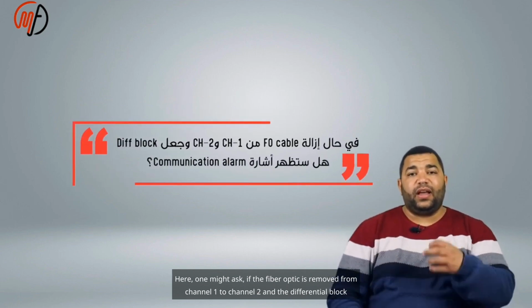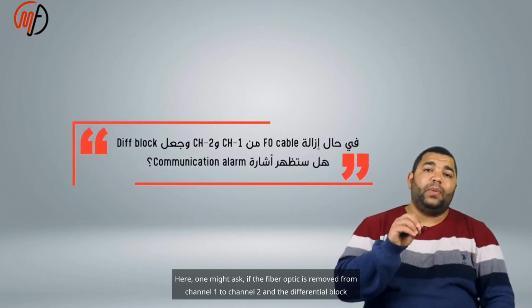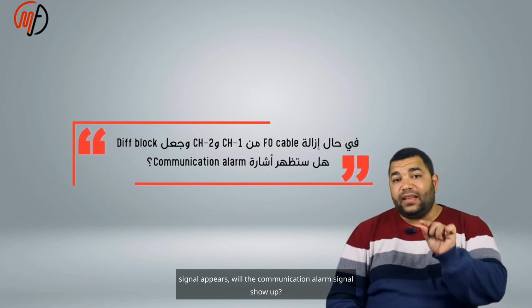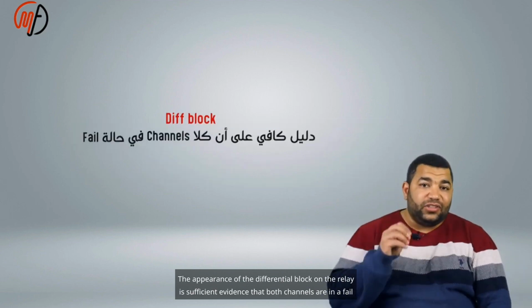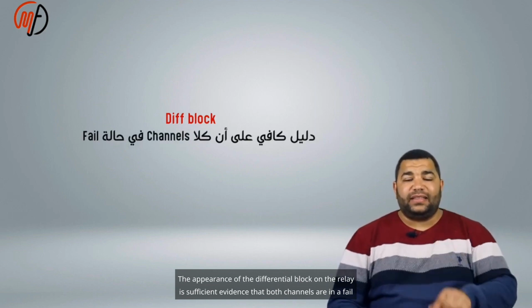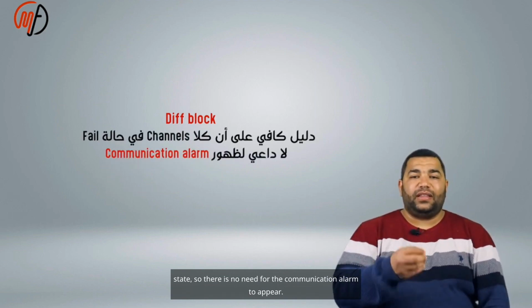Here, one might ask: if the fiber optic is removed from channels 1 and 2 and the differential block signal appears, will the communication alarm signal show up? The appearance of the differential block on the relay is sufficient evidence that both channels are in a fail state, so there is no need for the communication alarm to appear.